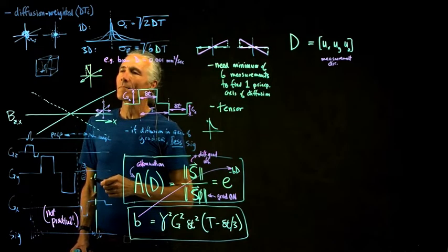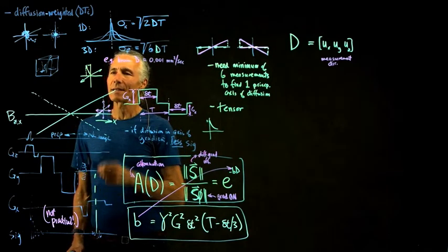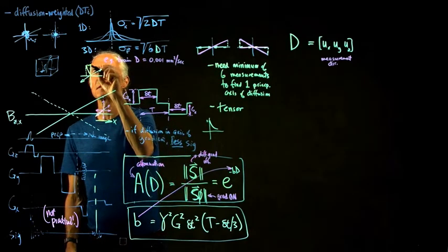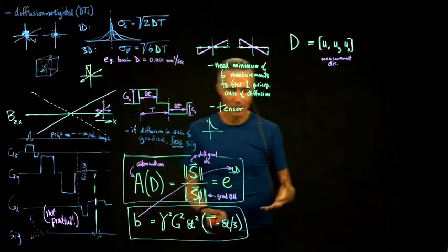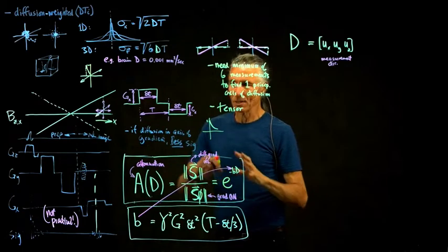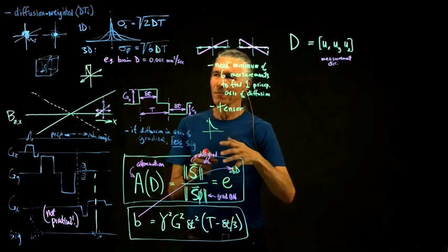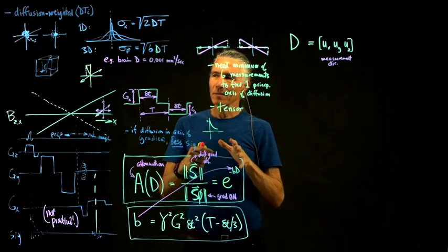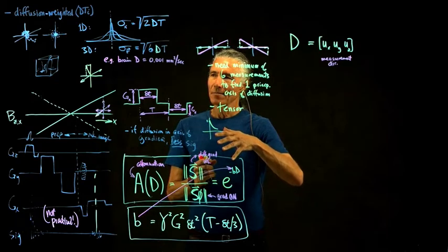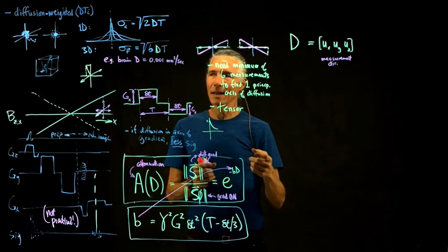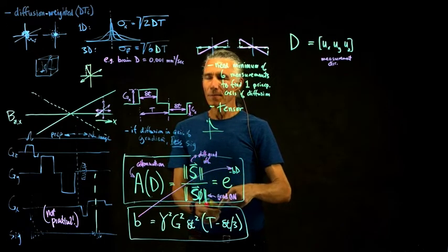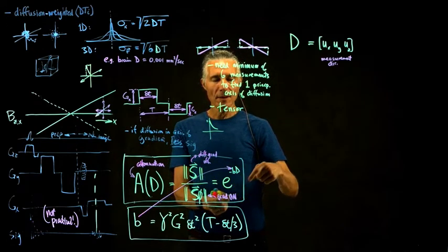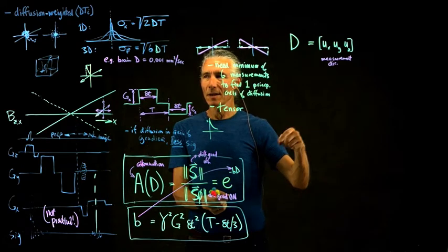A direction like that is going to be measured just by turning on 2 gradients. If you turn on 2 gradients, they'll just add to each other everywhere and effectively rotate the gradient. So turning on the X and the Y gradient at the same time will make a uniform change in the gradient moving along an axis in between the X and the Y gradient.